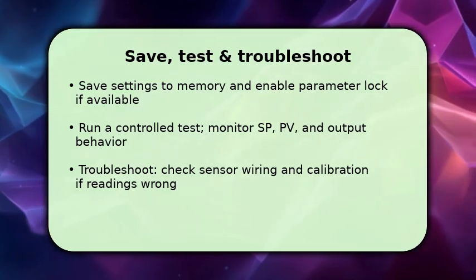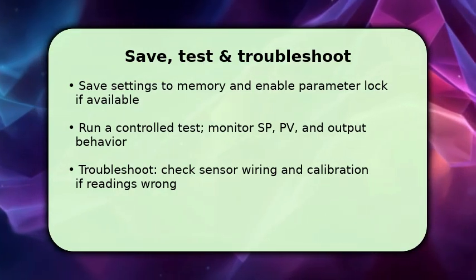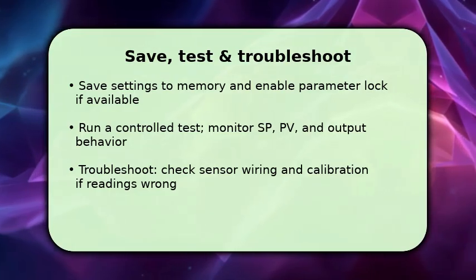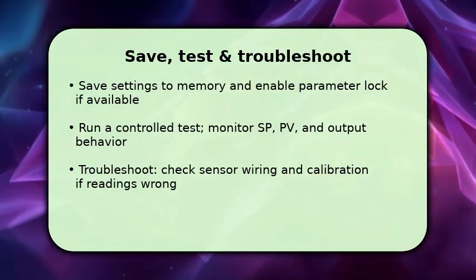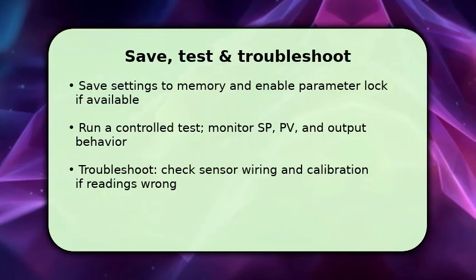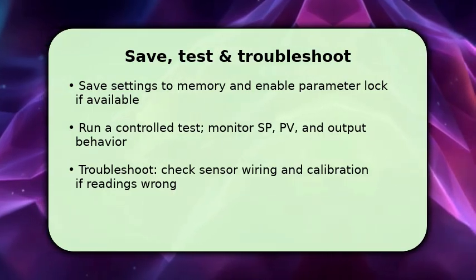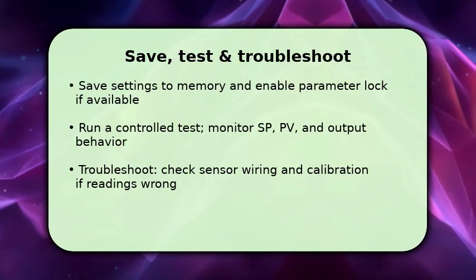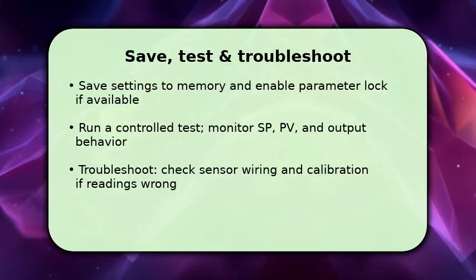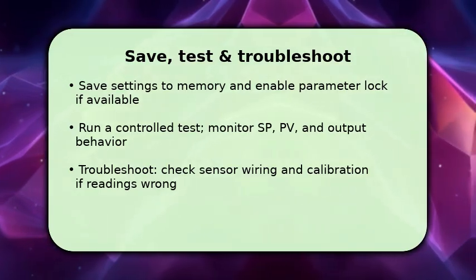If the controller behaves oddly, first verify sensor wiring, grounding, and probe calibration, because those cause most errors. If readings are stable but control is poor, return to PID tuning. If display shows sensor fault codes, replace or recalibrate the probe before further adjustment.